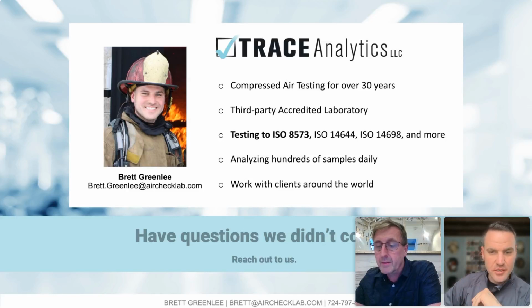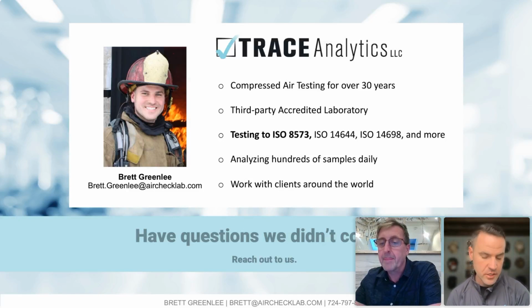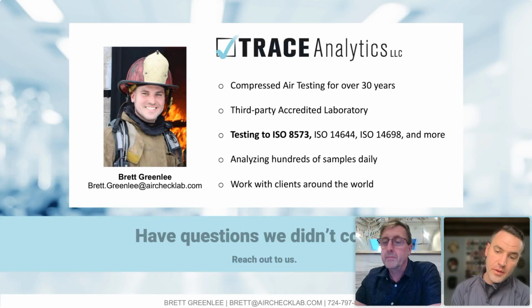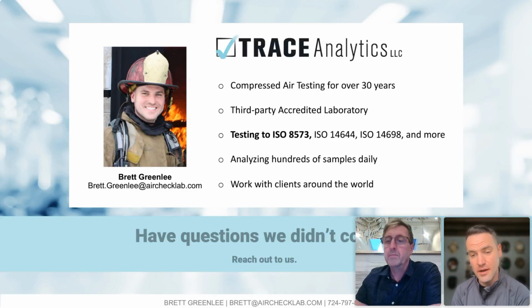Earlier in the presentation, I said a lot of words there for a moment, but limits for micro are not defined yet. That is coming very soon. We at Trace Analytics actually have folks on the ISO 8573 committee, and they tell us that limits for micro are coming soon. You'll have one of those purity class charts very similar to particulate, water and oil. All things microorganisms for ISO 8573 can be found in ISO 8573-7. Whatever is in there currently is what you will have. But hopefully very, very soon we'll have limits.